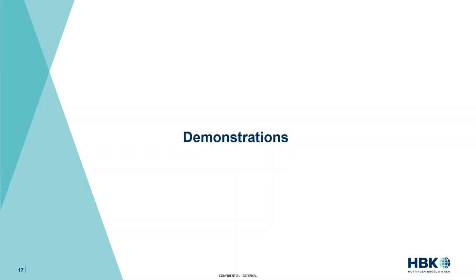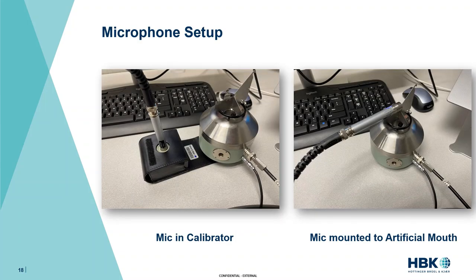Now for the fun stuff — seeing these apps in action. For the demo setup I have one of our microphones, I believe a 4189, first set up in one of our calibrators. After calibrating the mic I moved it over to the Type 4227 artificial mouth, a playback device designed to mimic human voice field and adhering to technical standards on speech playback. We'll go through the process of setting up, calibrating, and producing equalized speech out of the 4227.